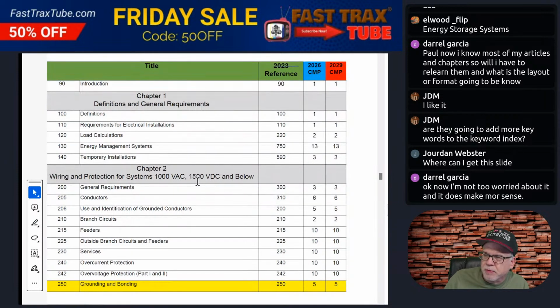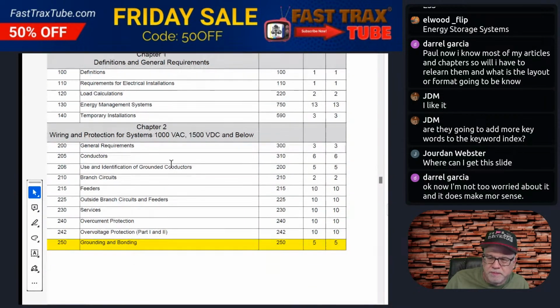Now let's look at chapter 2. Chapter 2 had general requirements for wiring and protection of 1,000 volts or less. It was in 300, it's going to be 200 now. You all know 200 was grounded conductors. Well, it's going to move. So 200 will be general requirements. 310, which is conductors, will now be 205. Use and identification of the grounded conductor, which used to be 200, will now be 206.